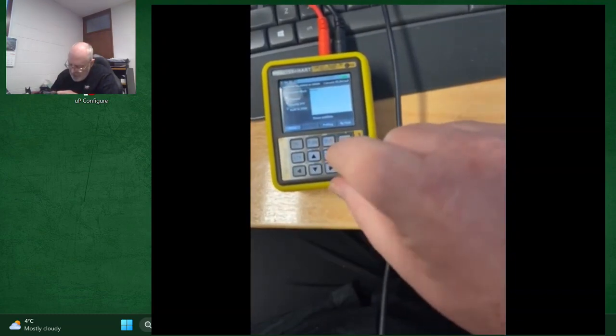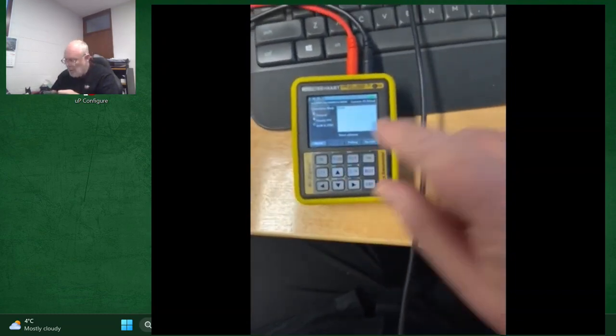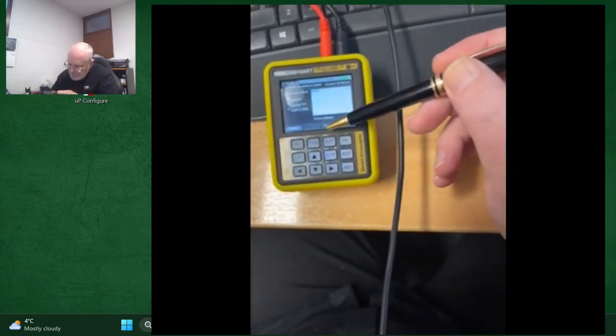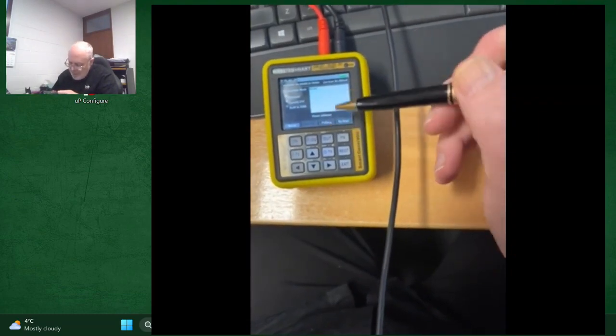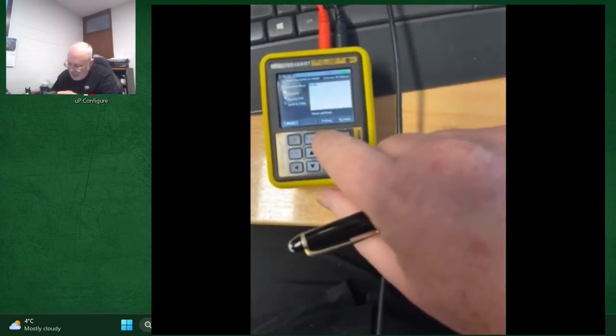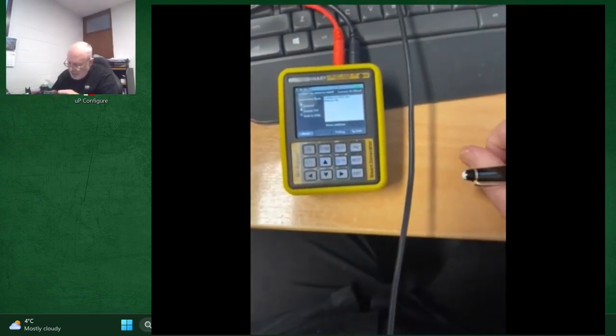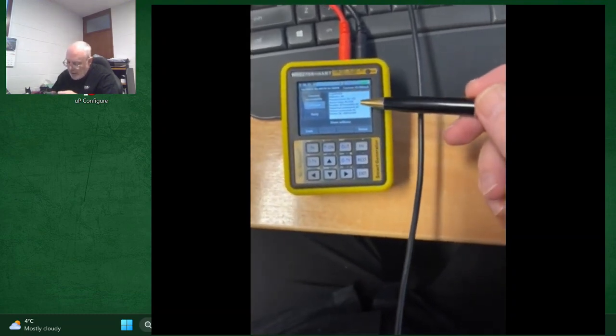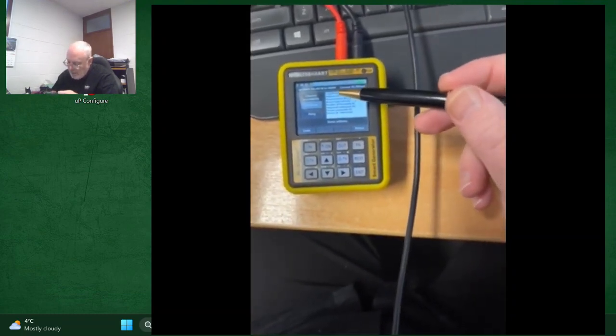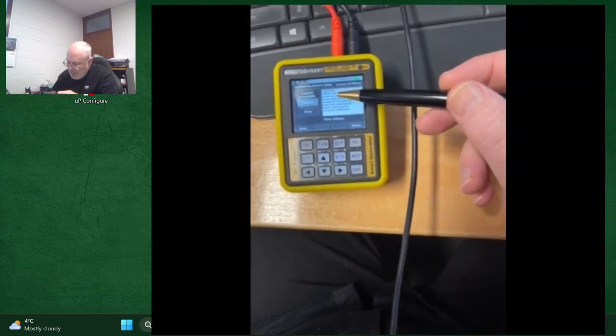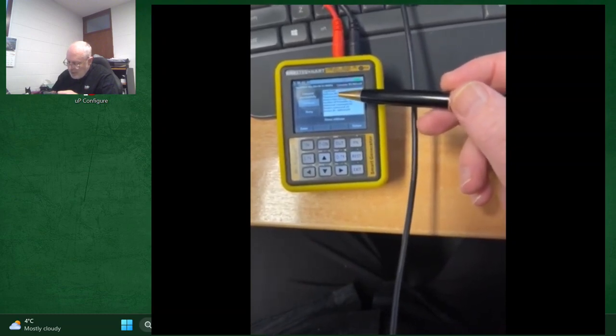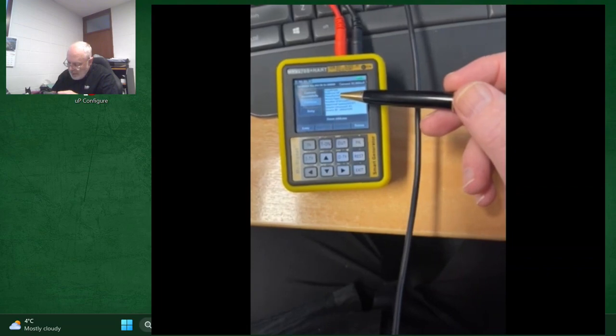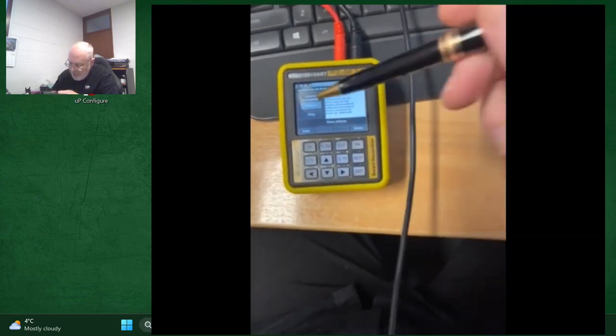So then if we hit the polling button, see the word polling on the soft button there, it will start searching through the addresses and we see straight away it comes up with a tag, NP400, its address on HART, preamble to each details etc.